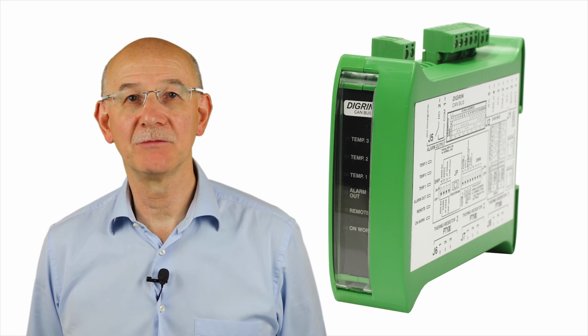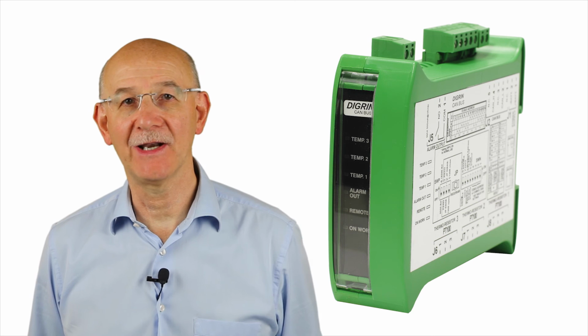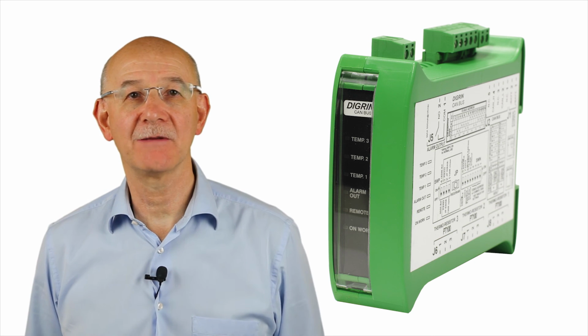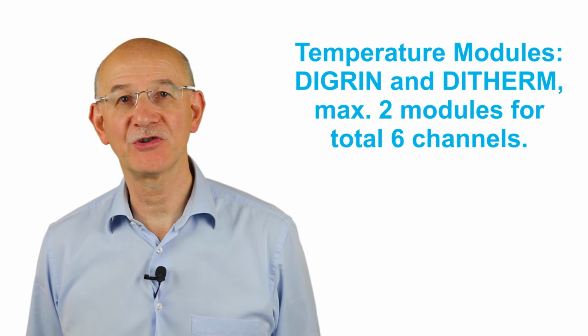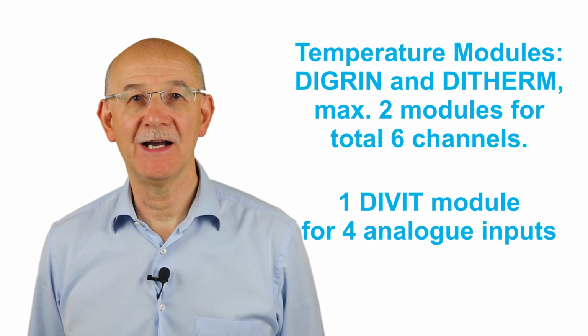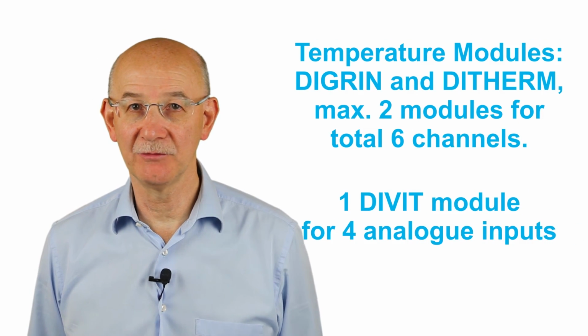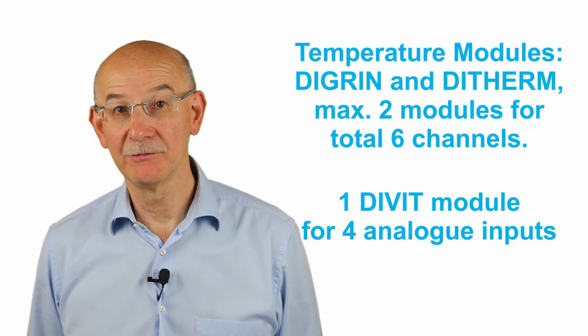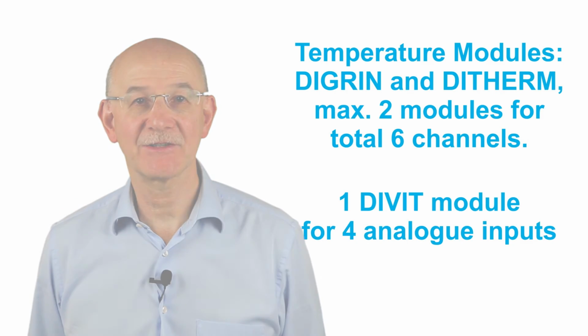Analog inputs can be expanded by external modules. Up to 2 temperature modules, DIGRIN for PT100 or DITHERM for thermocouple, can be added for a total of 6 temperature channels. An additional analog voltage current input module can be added too, for a total of 4 channels.